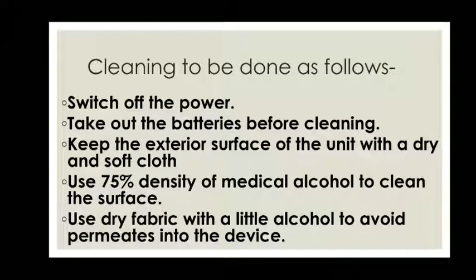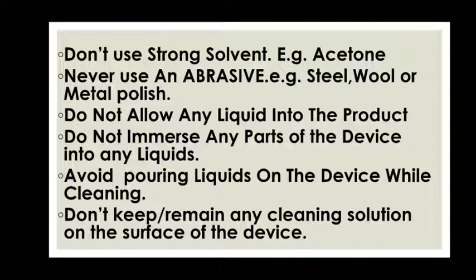So cautions while cleaning. Don't use a strong solvent, for example acetone, just like nail paint remover. Never use an abrasive like steel wool or metal polish. Do not allow any liquid into the product. Do not immerse any parts of the device into any liquids. Avoid pouring liquids on the device while cleaning. Don't keep or leave any cleaning solution on the surface of the device. Make it dry. Whatever you are using, make it dry.